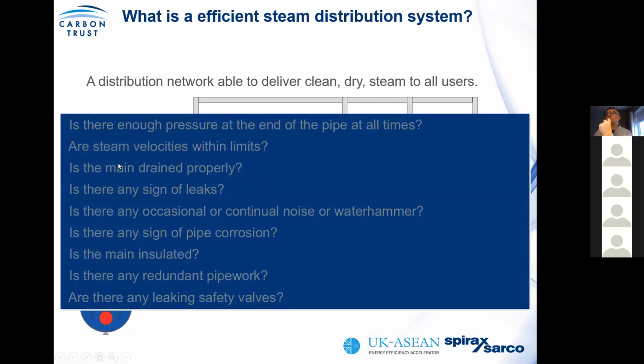So what you need to consider is that on your distribution system, for your end users, do you have enough pressure? In other words, do you see pressure swings at some end users? If that's the case, you would have to look at pressure management. So in other words, increase the distribution pressure to compensate, because where there is a certain pressure, a pipe has a certain capacity to carry steam. Increasing the pressure means it can carry more steam more effectively at reduced velocities. So again, what you want to do is reduce the velocities in your system.